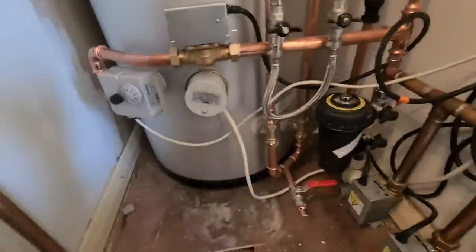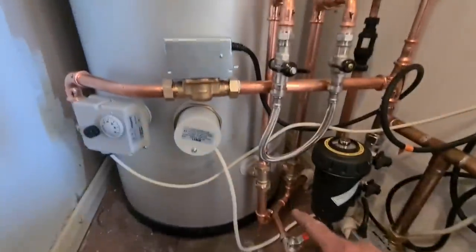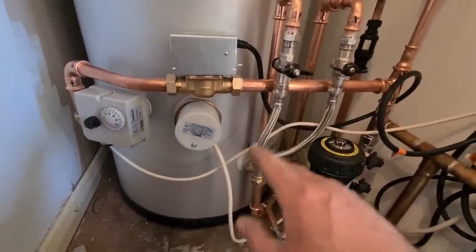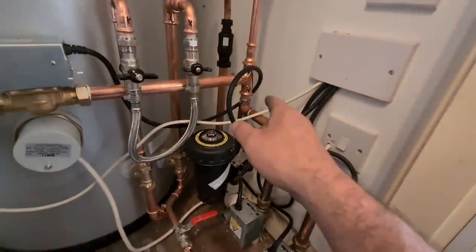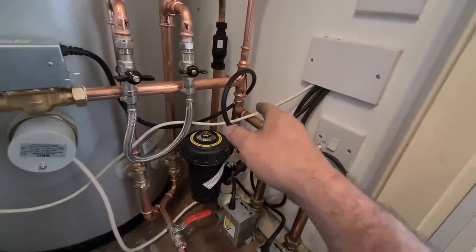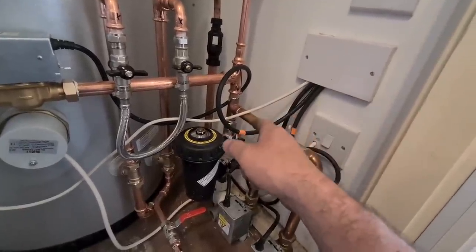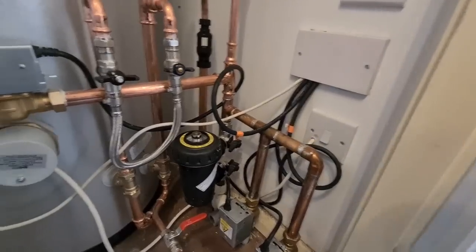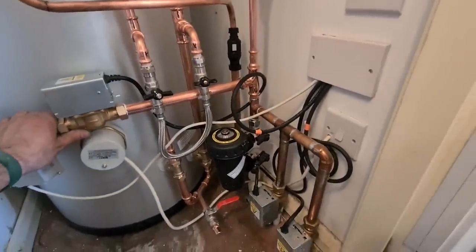But again, quick insight, our flow in, S-Plan Plus. I do need to speak up, potentially make it domestic hot water priority. But what I need to do there is look to put an additional port in there now. A normally open one, so I could put it here, bridge it, and do it in all the controls. But with the Part L, speak to client about that.